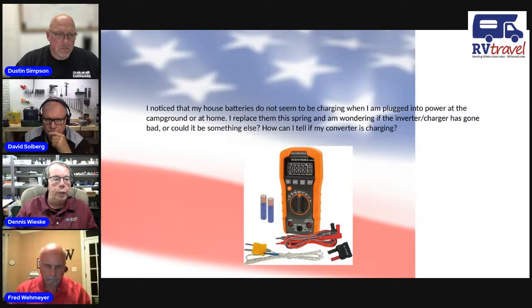It's critical to know the voltage at the charger and the voltage at the battery. If your charger is putting out voltage like I showed before, anywhere from 13.2 to 14.4, you should be seeing voltages above 13 volts at the battery. That will depend on how much current is being drawn and how much wire loss and voltage drop there is between the battery and the converter, but generally you should see over 13 volts. If you're seeing 12.5 volts or 10.5 volts instead, that charge voltage isn't getting to the battery, and that's when you need to check - usually it's your battery protection device or short-stop circuit breaker. Occasionally it may also be your disconnect switch, or a bad connection anywhere between the converter and the battery.